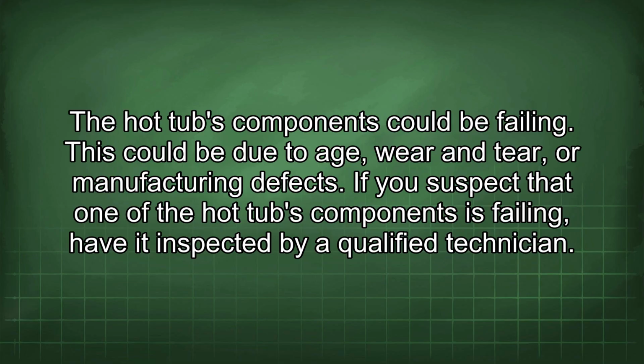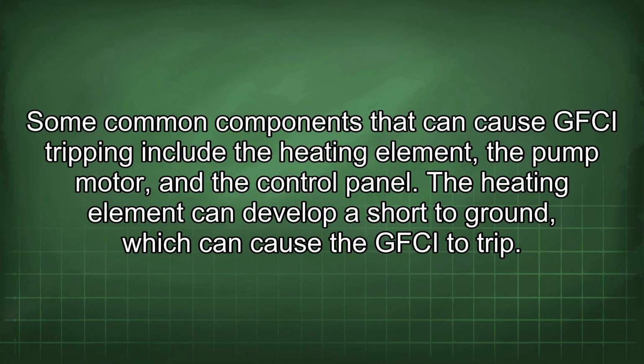The hot tub's components could be failing. This could be due to age, wear and tear, or manufacturing defects. If you suspect that one of the hot tub's components is failing, have it inspected by a qualified technician. Some common components that can cause GFCI tripping include the heating element, the pump motor, and the control panel.